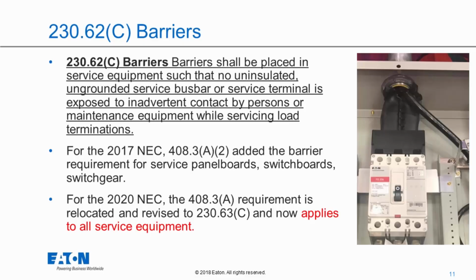If you look at the 2017 NEC and went to Article 408.3(A)(2), you would see language similar to this that required barriers for service panelboards, switchboards, and switchgear. In the 2020 NEC, we've relocated that from Article 408 into Article 230, so now it applies to all service equipment. It could be a panelboard, switchboard, switchgear, a disconnect switch, or an automatic transfer switch. Any equipment used as service equipment must now have barriers such that no uninsulated, ungrounded service busbar or service terminals is exposed to inadvertent contact by persons or maintenance equipment while servicing load terminations.